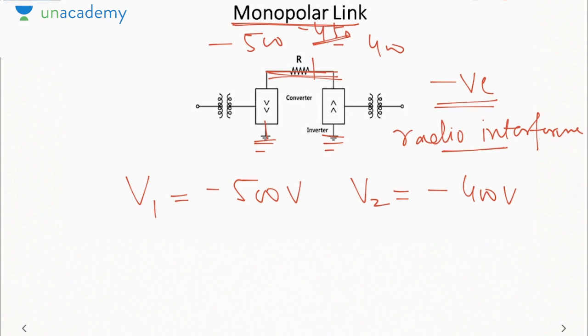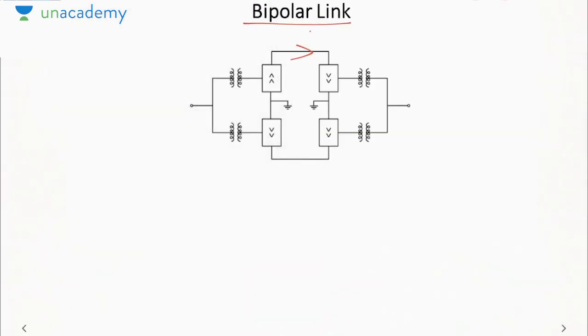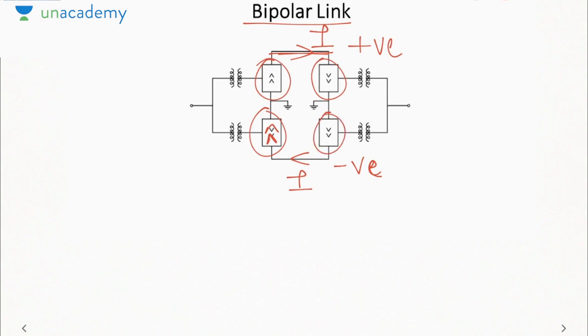That is, the voltage at every point on the conductor will be negative. Similarly, if you use two conductors, one as the forward path and one as the return path, it is called a bipolar link, because one conductor will have positive polarity and the other negative polarity. That is, one conductor will have all voltages greater than 0, the other all voltages lesser than 0. Okay, so kindly correct this. This will also be pointing upwards. These two are rectifiers. These two are inverters. Here the benefit is that if this conductor breaks down, then we will operate this link as a monopolar link with ground as the return path. So that is the advantage.